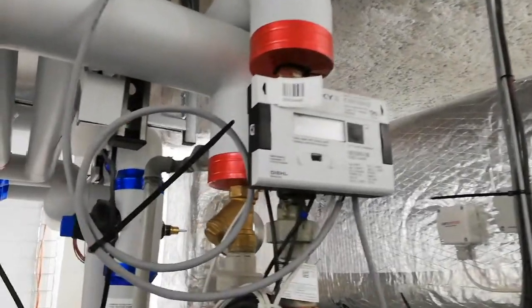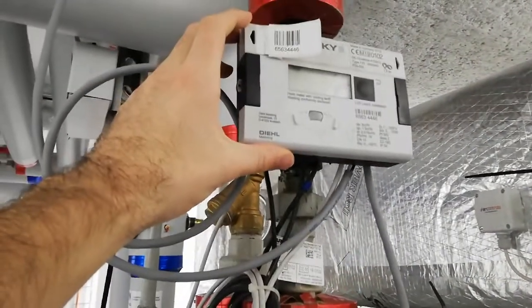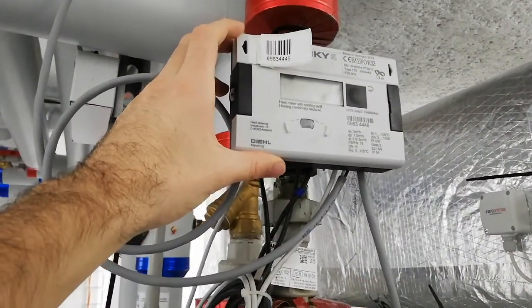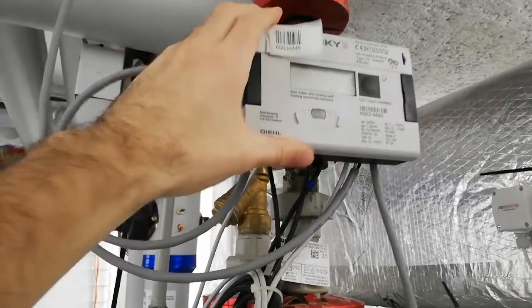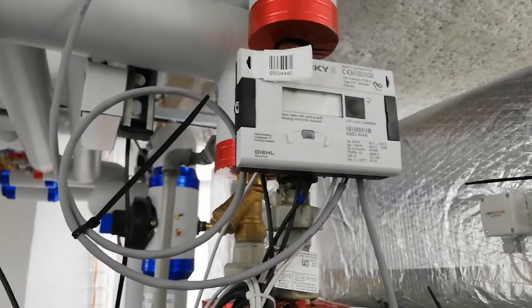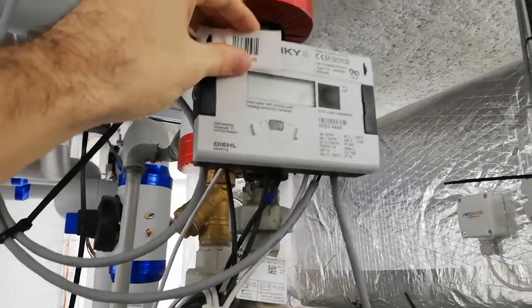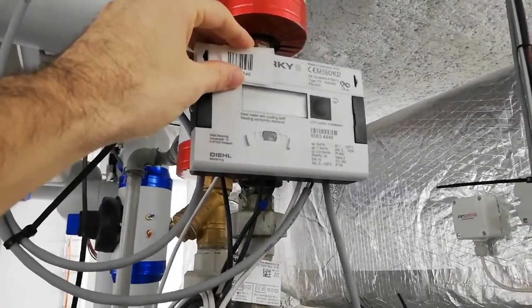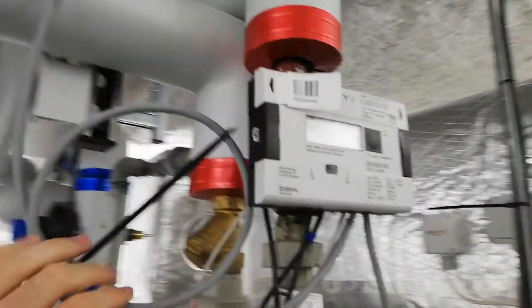These energy meters are able to communicate with the BMS system, so don't forget to ask for the communication card. For this system it is LonWorks, so we had to ask for a LonWorks communication card to install. And here you have the wire going to the BMS system.